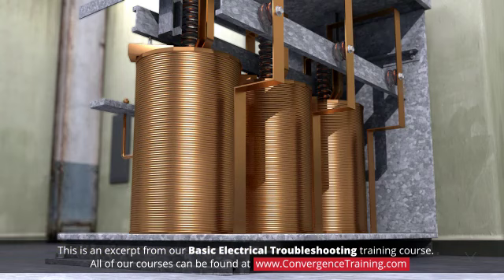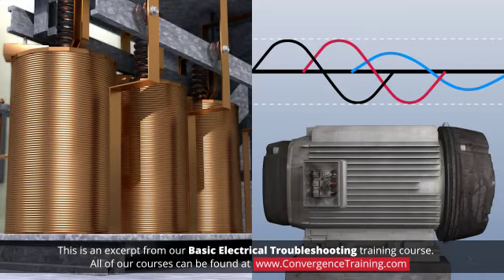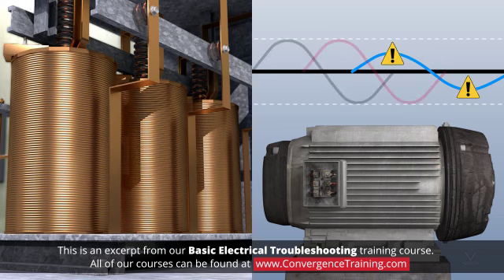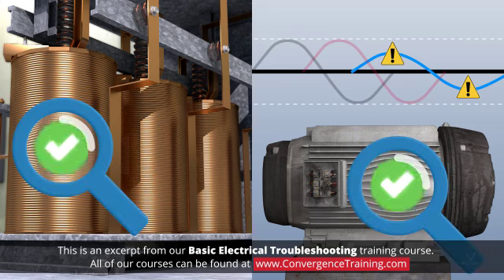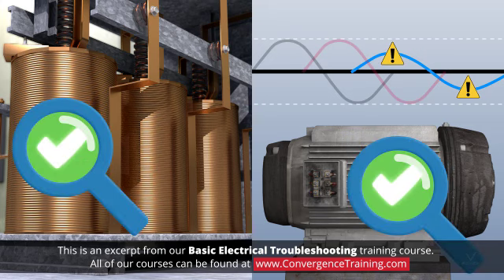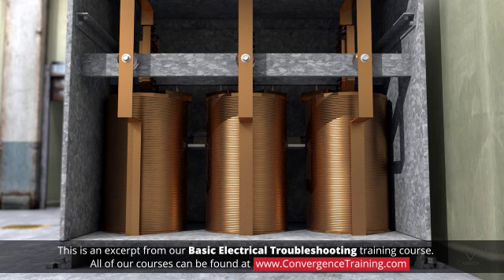Three-phase transformers have electrical similarities to three-phase motors and can be troubleshot in a similar fashion. They share the characteristic that one leg or winding can be bad, but the overall device can appear to be functioning correctly.